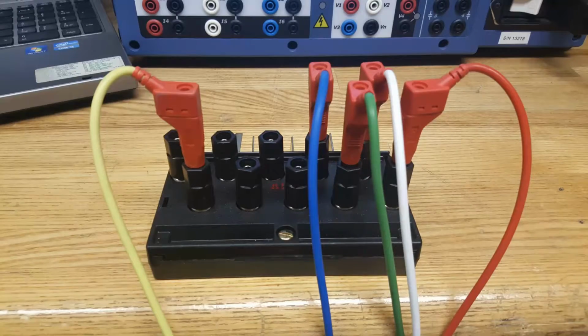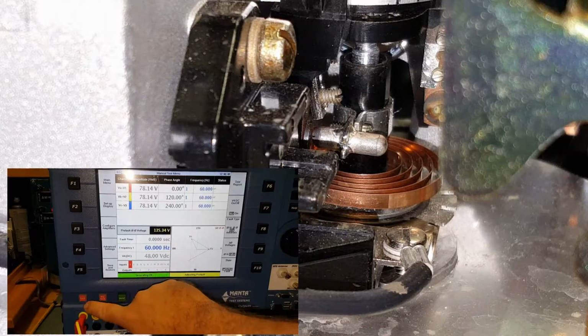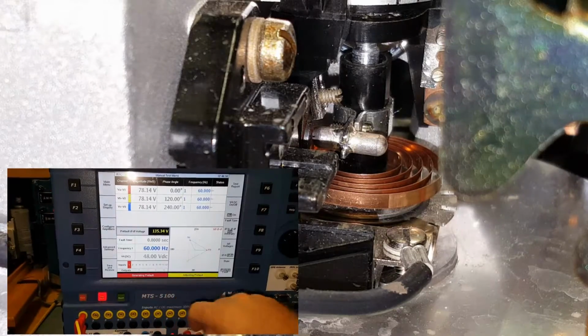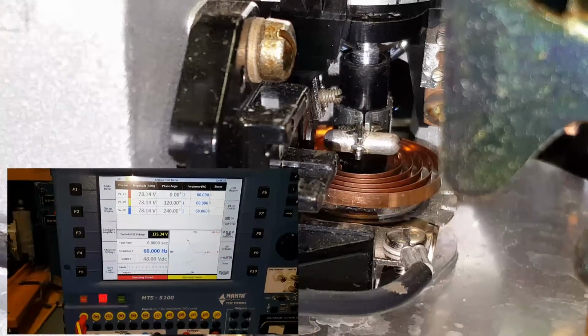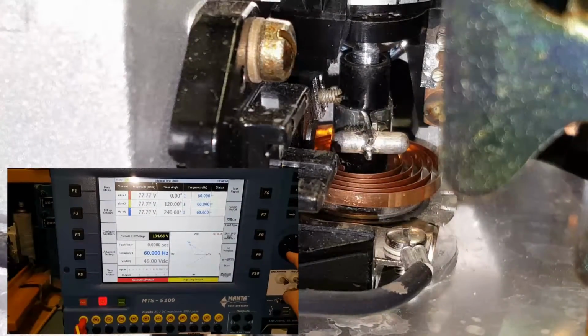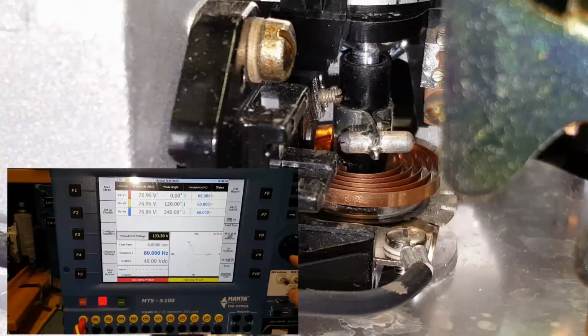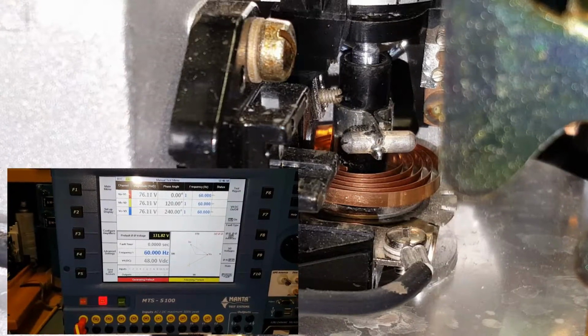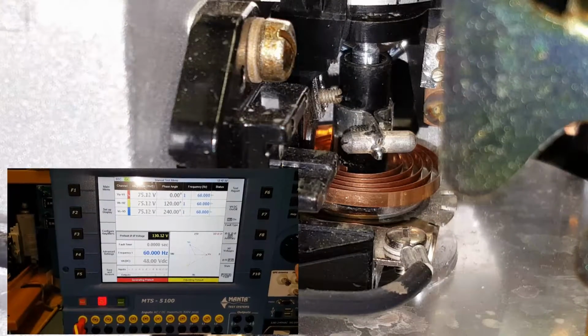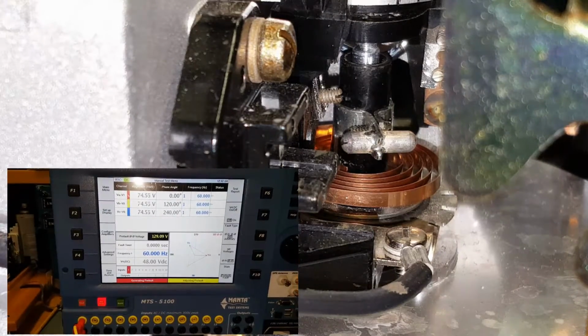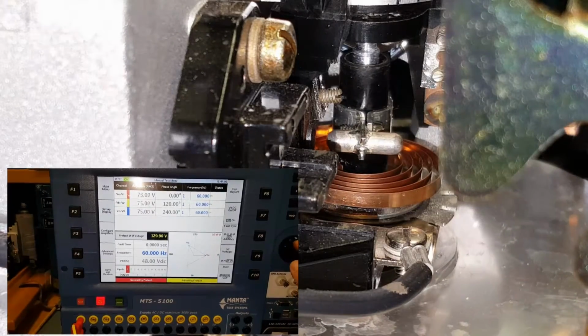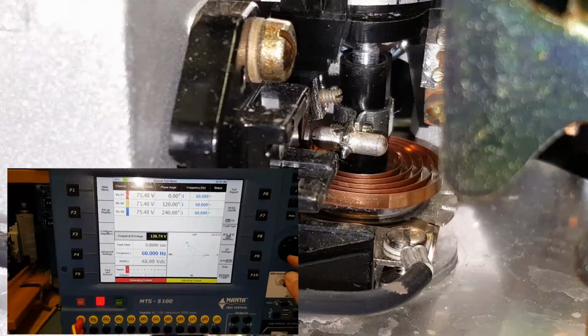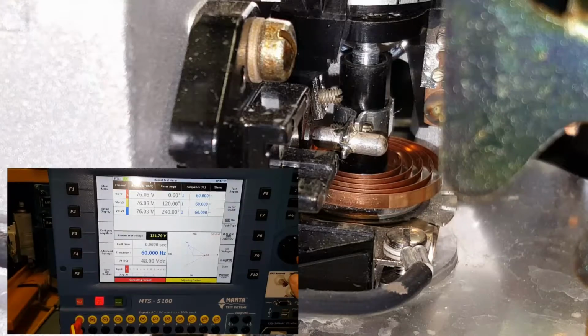For the undervoltage, we're going to move sensing to 2 and 10. Similar to the overvoltage pickup test, with the undervoltage pickup test, we're going to take the nominal value plus or minus 10%. We're going to bring the voltage above the low voltage pickup. We're going to back it off a little bit, bring it back up, once again back down. That way we know exactly where the low voltage pickup is going to be and then record our value.